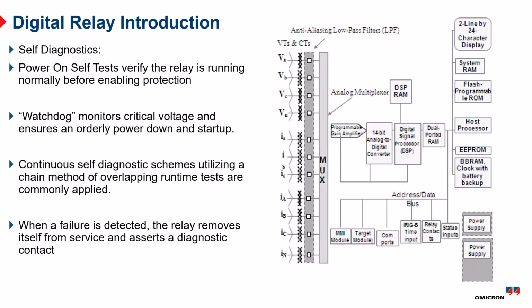A lot of relay manufacturers talk a lot about their self-diagnostics, and I remember even a long time ago, the self-diagnostics were quite extensive. Just as an example, in the Beckwith, there were two test channels here, a reference channel, which was a maximum input, and a ground channel, which was a minimum input. So every time the relay sampled all these inputs, it tested the reference channel and the ground input. If those were out of spec, the relay would take itself out of service and close the diagnostic contact, telling us, hey, I'm broke.